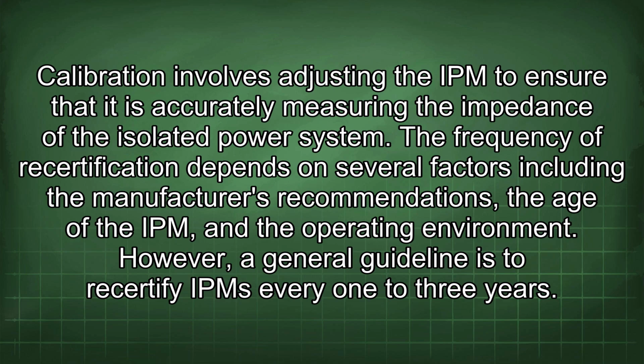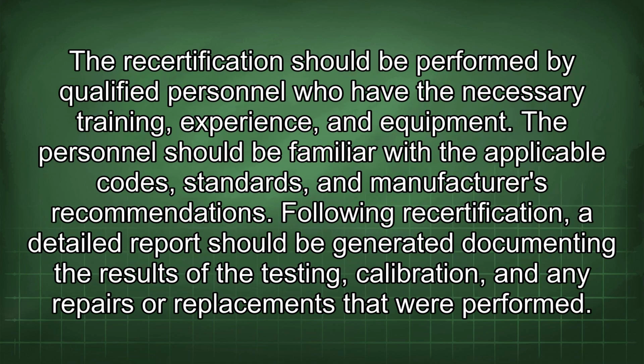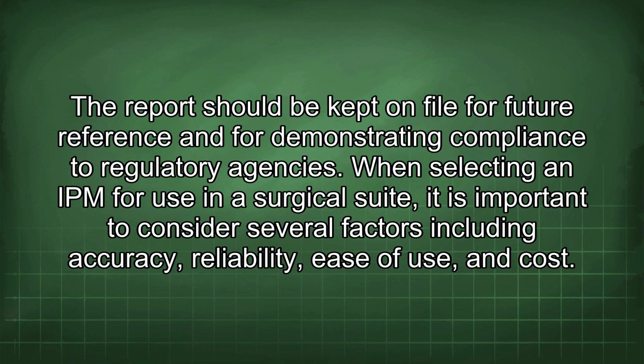system. The frequency of recertification depends on several factors, including the manufacturer's recommendations, the age of the IPM, and the operating environment. However, a general guideline is to recertify IPM every 1 to 3 years. The recertification should be performed by qualified personnel who have the necessary training, experience, and equipment. The personnel should be familiar with the applicable codes, standards, and manufacturer's recommendations. Following recertification, a detailed report should be generated documenting the results of the testing, calibration, and any repairs or replacements that were performed. The report should be kept on file for future reference and for demonstrating compliance to regulatory agencies.